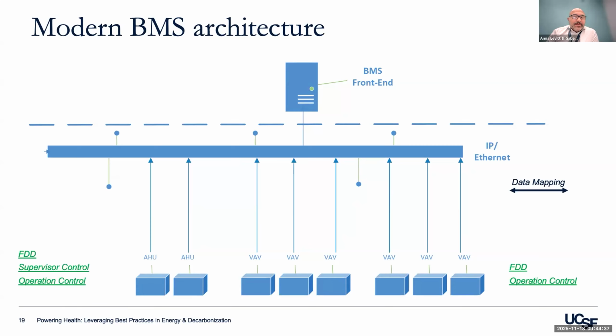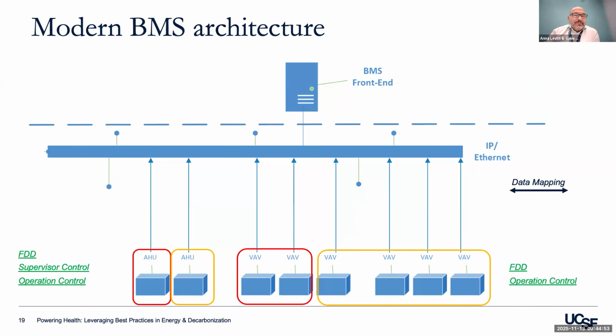Thinking about Guideline 36 again and what it recommends, a lot of that logic then gets pushed down directly into the BMS system. When you focus on a similar situation where you had VAVs going to one air handler and others going to another, the mapping becomes a little bit simpler, though it can still become complicated. Like in the case Anna mentioned, at Bayfront we have 6 air handlers, and you may have 50 to 100 VAVs being mapped to each air handler.